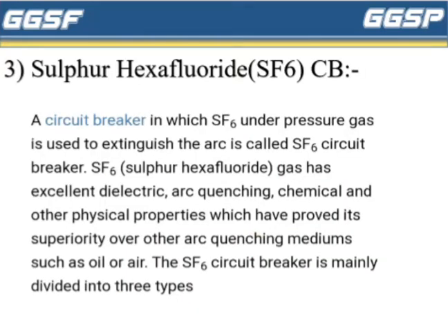Sulfur hexafluoride, that is SF6 circuit breaker. A circuit breaker in which SF6 under pressure gas is used to extinguish the arc is called an SF6 circuit breaker. SF6 gas has excellent dielectric, arc quenching, chemical and other physical properties which have proved its superiority over other arc quenching mediums such as oil or air.